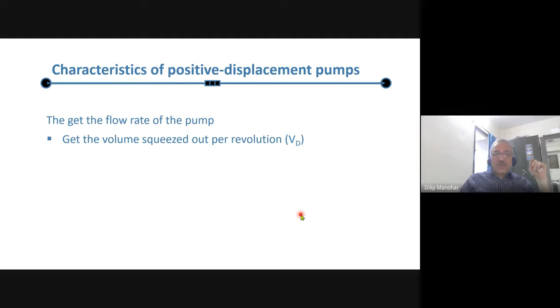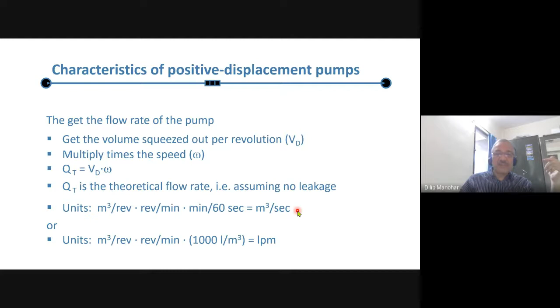Now, what are the characteristics of the positive displacement pump? How do we get the flow rate? You take the volume squeezed out per revolution and multiply by the speed of rotation. So the theoretical discharge Qt is the volume squeezed out per revolution, Vd, times omega. There is no leakage here, we assume. The units are meter cube per revolution times radians per second, so it's meter cube per second, or another unit could be liters per minute. Both units are very popular in calculation.